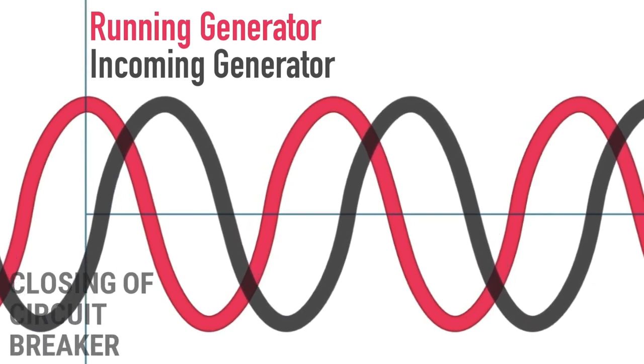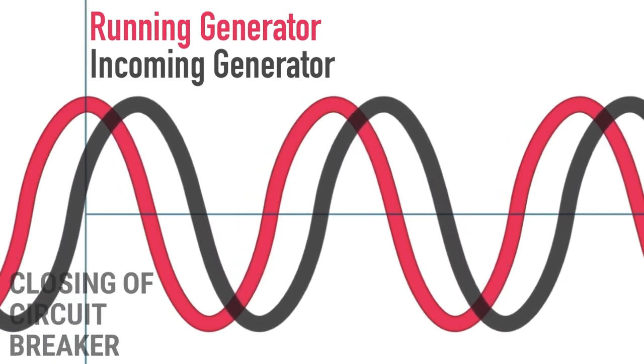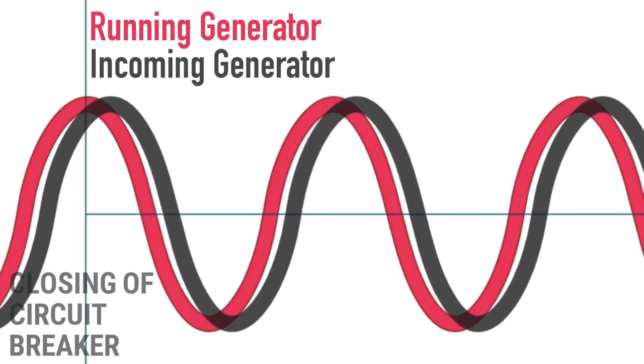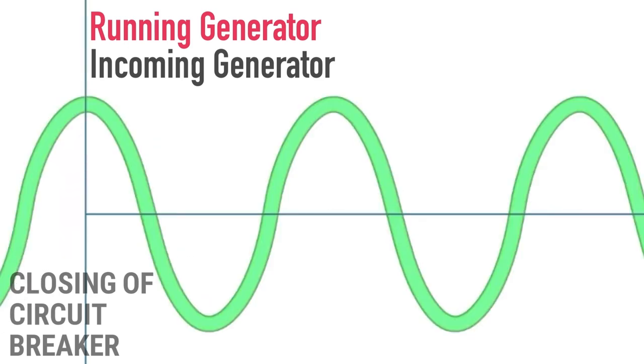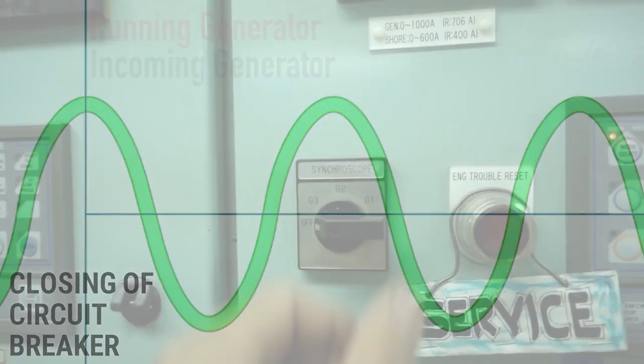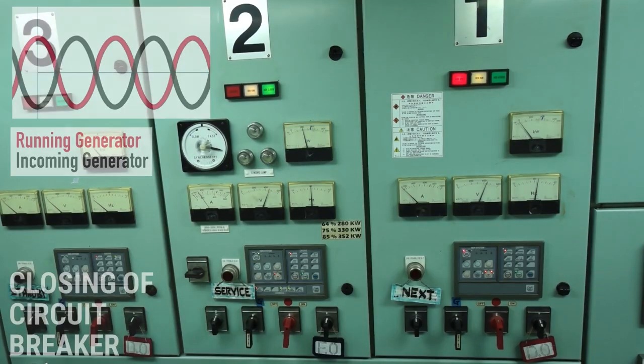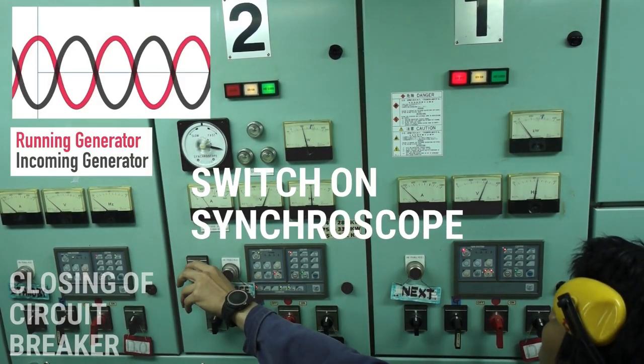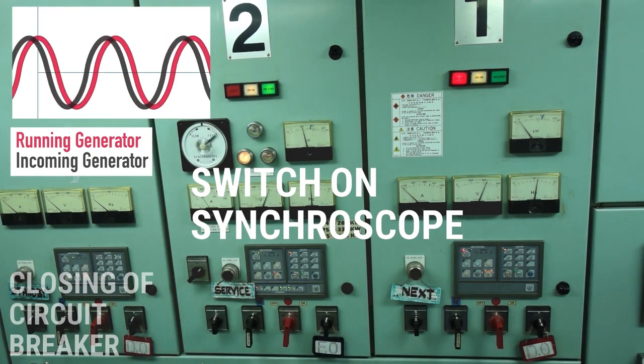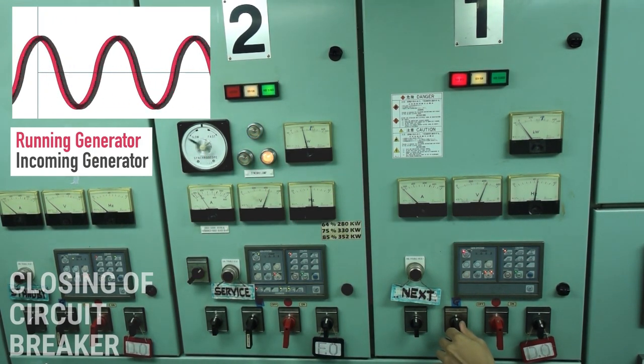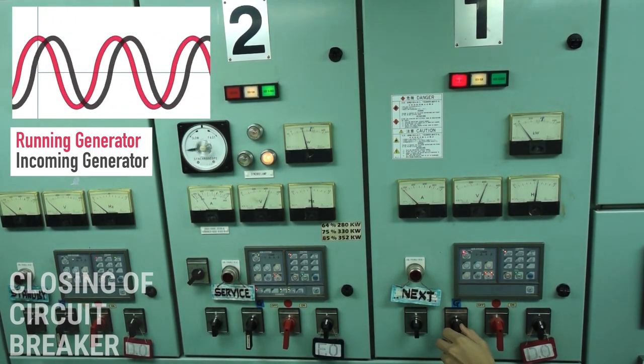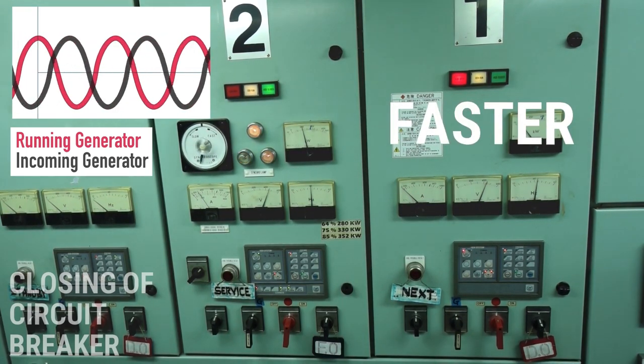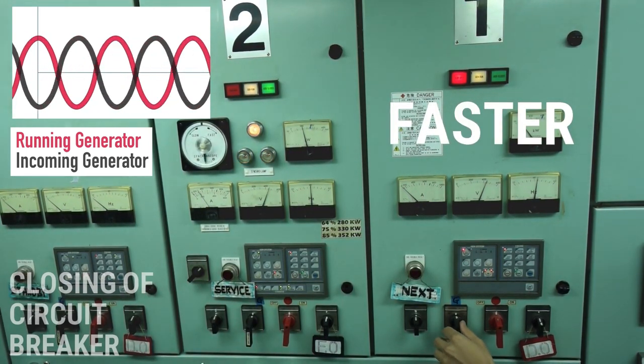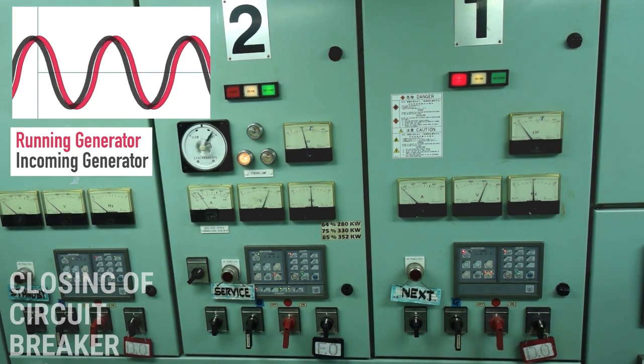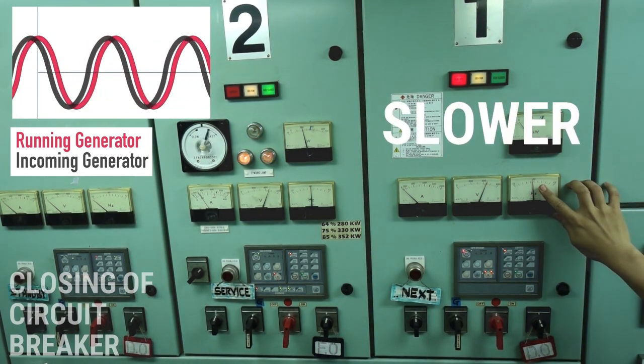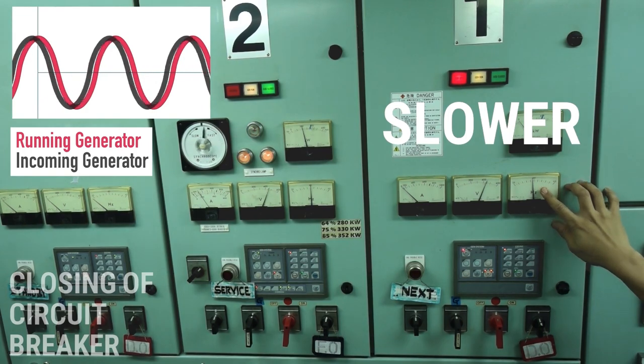To close the circuit breaker, the incoming generator circuit breaker must be closed when their frequency angles are in sync. Switch on the synchroscope and select the incoming generator. The synchroscope must be rotating slowly clockwise. This means that the incoming generator's frequency is slightly faster than the running generator. If the synchroscope is rotating counterclockwise, it means that the frequency is slower than the running generator.